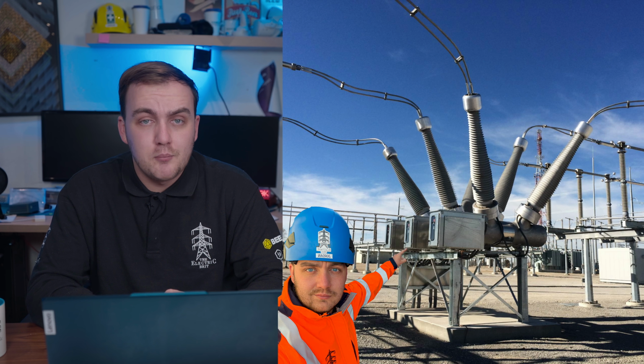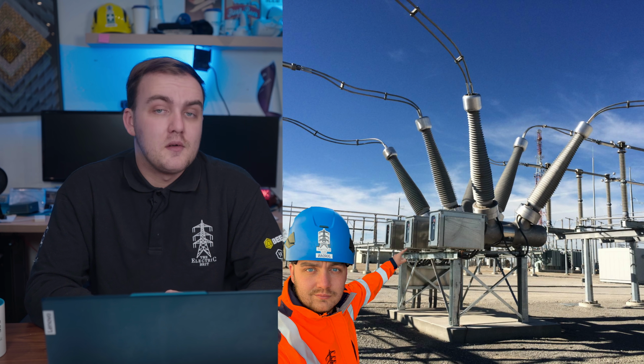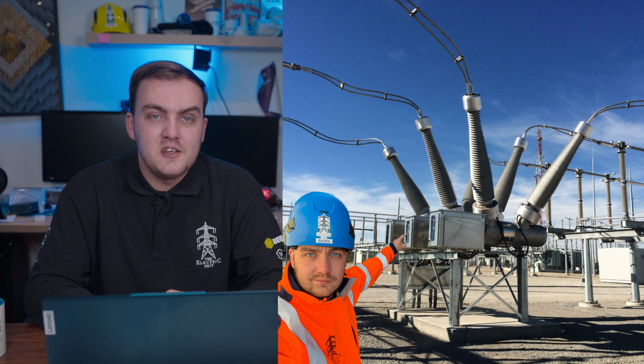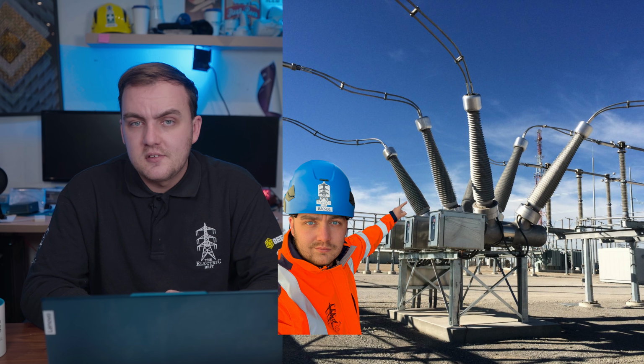For a quick recap, a circuit breaker is used to break a live electrical circuit under load, and especially under fault conditions, which could be many times the normal load current, and it needs to do it safely without rapidly disassembling, again and again, reliably. This one is a dead tank because you can touch the metalwork and mechanisms at the bottom without getting a shock, because the high voltage bit is supported by these bushings, the spiky discs sticking out of the tank.